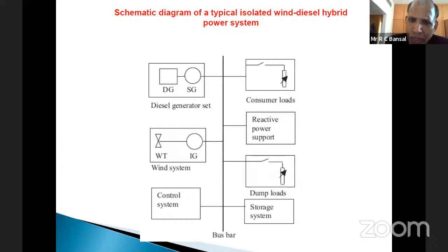We also have to ensure balance between reactive power generation and demand. If there's a mismatch, it causes voltage deviation. Reactive power support can come through capacitor banks or more advanced support like static VAR compensators, so we need suitable reactive power support as well.